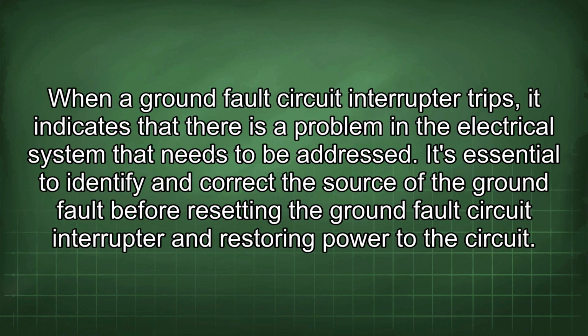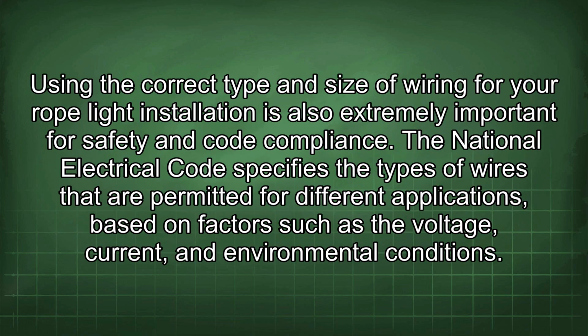When a ground fault circuit interrupter trips, it indicates that there is a problem in the electrical system that needs to be addressed. It's essential to identify and correct the source of the ground fault before resetting the ground fault circuit interrupter and restoring power to the circuit. Using the correct type and size of wiring for your rope light installation is also extremely important for safety and code compliance. The National Electrical Code specifies the types of wires that are permitted for different applications based on factors such as the voltage, current, and environmental conditions.